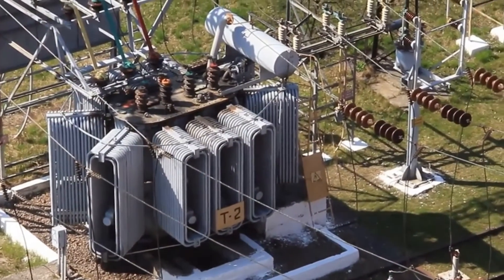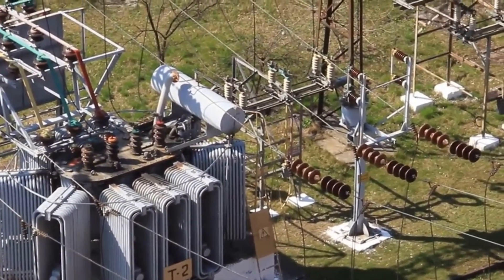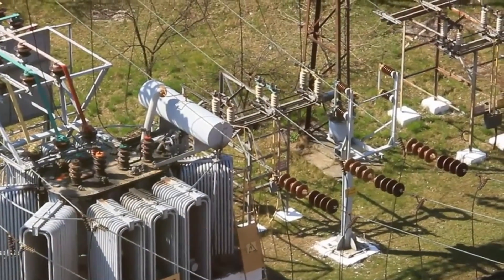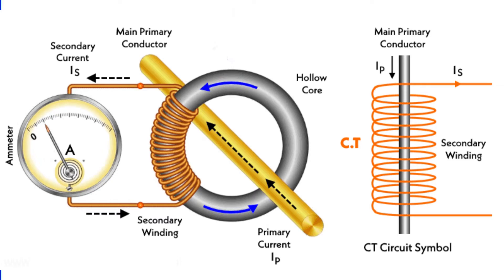The CT differs significantly from a power transformer, which operates on mutual inductance, as the CT's primary current is dependent on the load current. This characteristic ensures that a CT's primary current remains consistent, irrespective of whether its secondary is connected with a burden or not. This critical information helps us understand the risks associated with an open secondary winding in a CT.